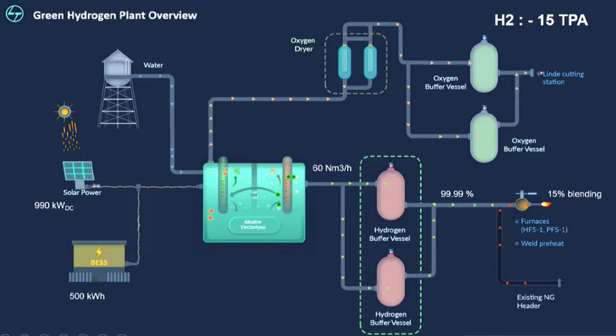We also installed a battery energy storage system, because if we had to start the electrolyzer every morning and stop it at night, the startup and shutdown times were quite high, around 45 minutes to 1 hour from cold conditions. With the battery energy storage, we maintained hot standby conditions, keeping critical operations like the KOH circulation at around 60-65 degrees Celsius, enabling us to quickly ramp up the plant as soon as solar energy is available, in less than 10 minutes. That's an innovation we did here.